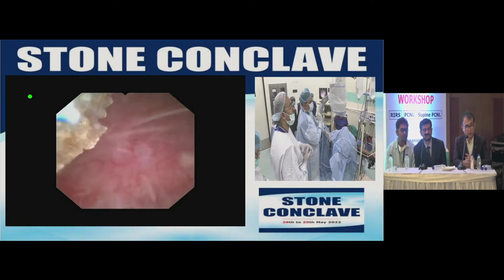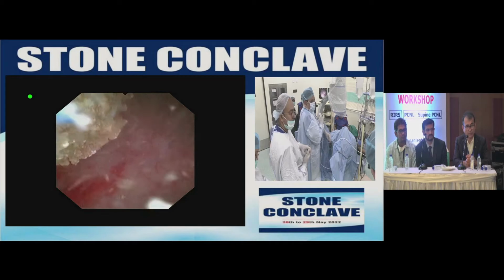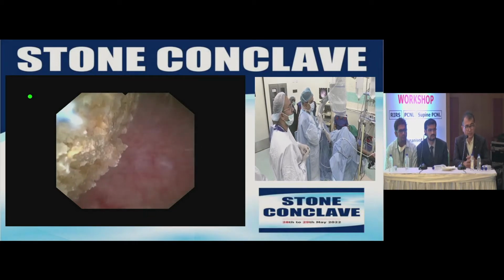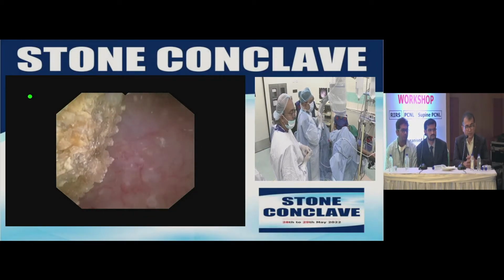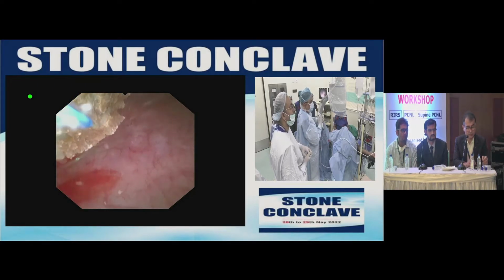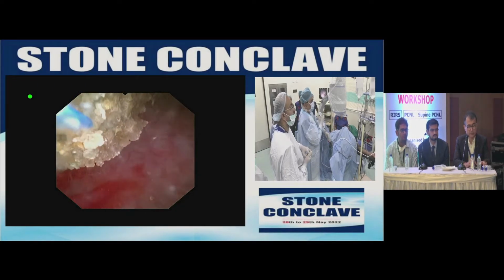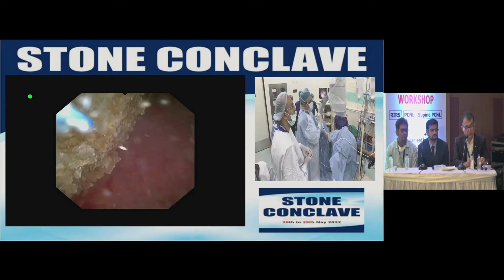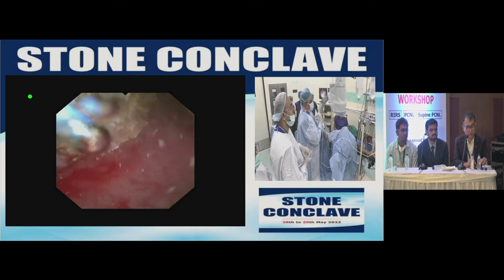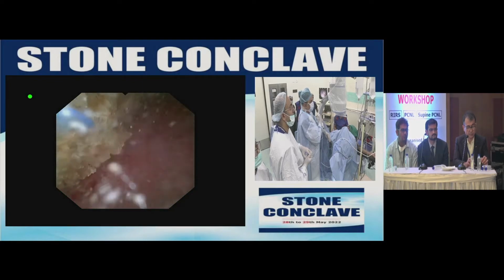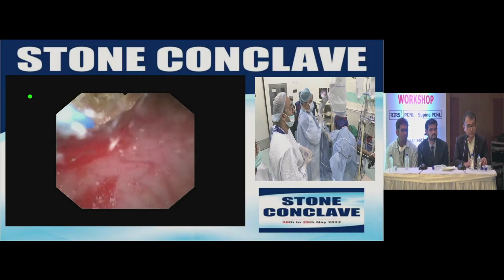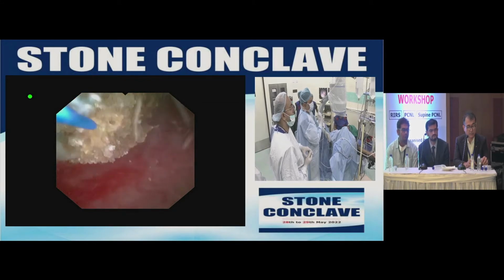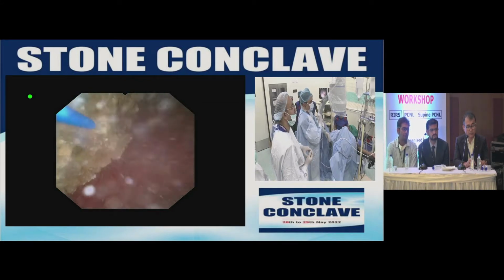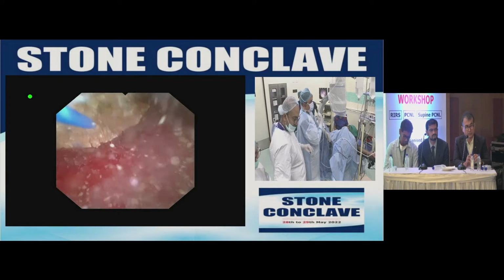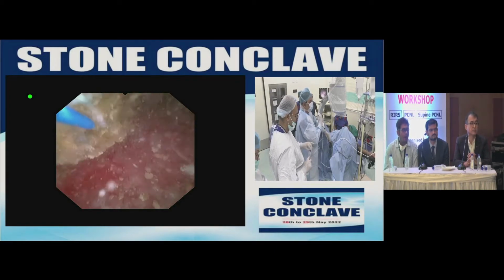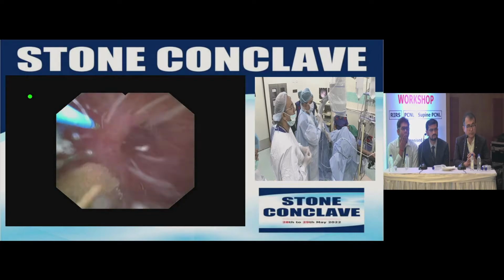In this particular case, what is the frequency? Right now, the frequency is 15 and the energy is 0.7. So total power which we are using is 10.5 watt. Now, there is a discussion that why do you need to use a thulium fiber laser if you are not using frequency at maximum, which is a possibility with the thulium fiber? Then what is the point of buying a thulium fiber laser? That is another question. Now it is said that thulium fiber laser is 4 times speedier than the holmium laser.